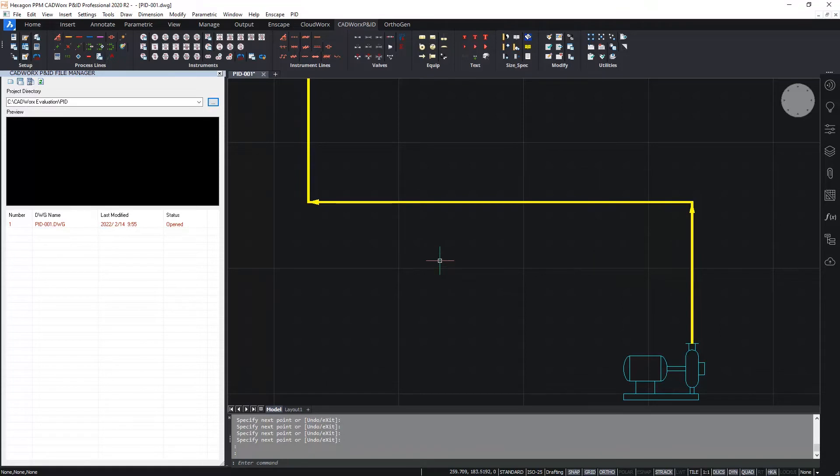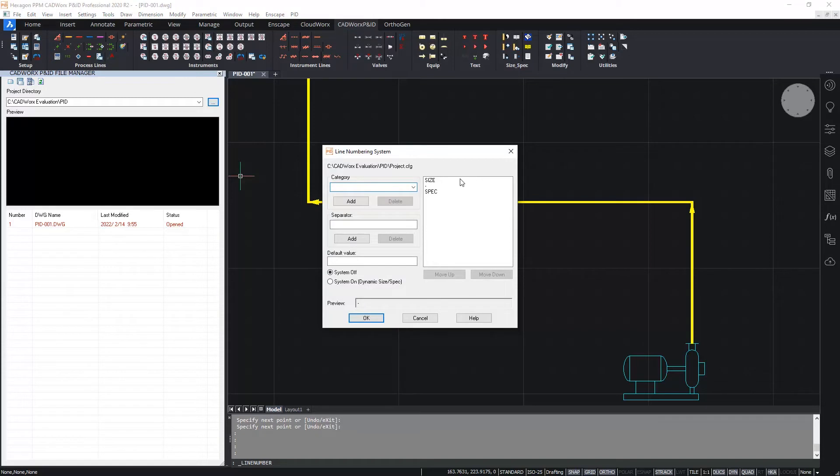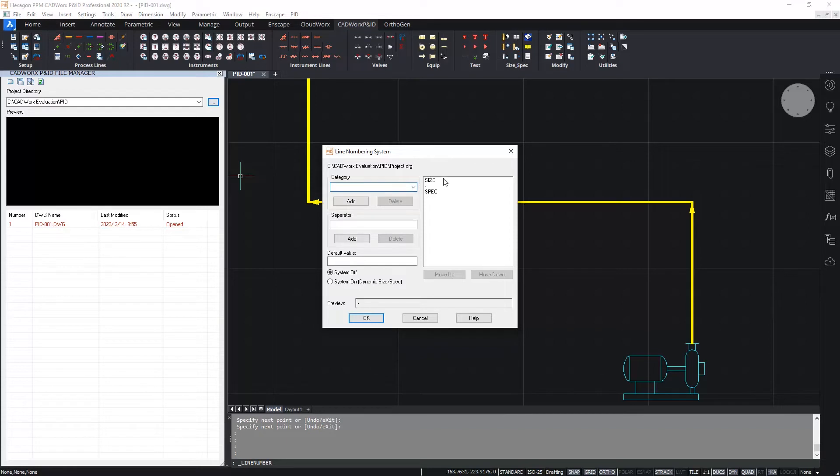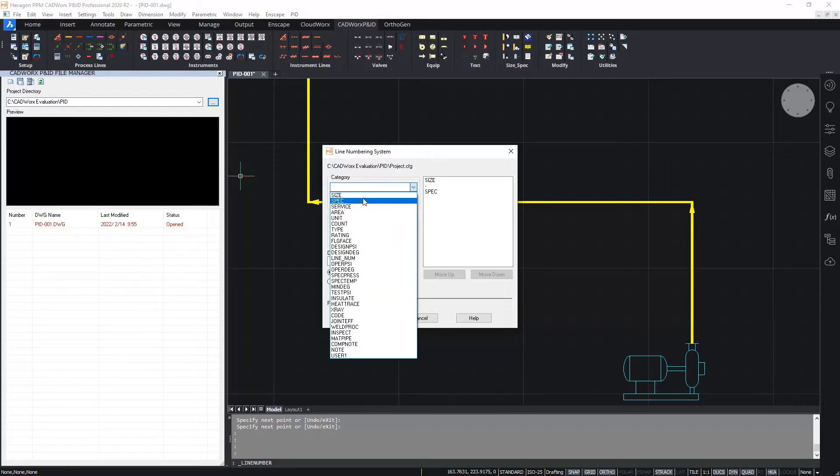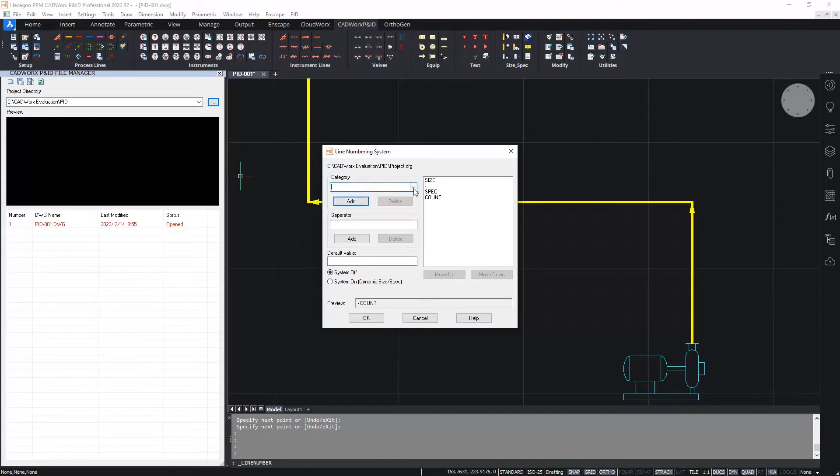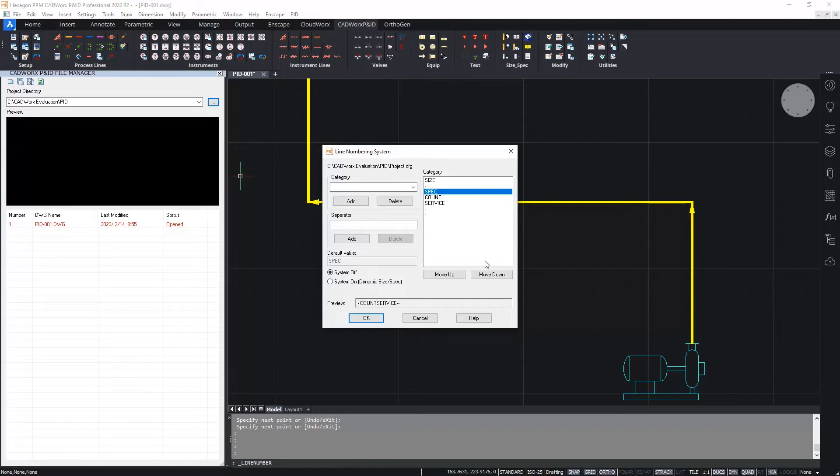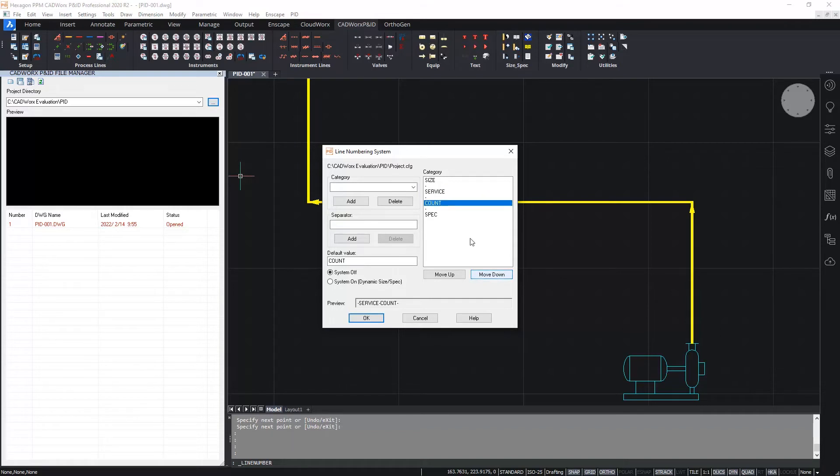However, for more consistent tagging, I'm going to configure a line numbering system. I'm going to select the line numbering system icon on the ribbon over here. And I will now set up my line numbering system. I can choose from any available category in the process lines table in the project database. I already have size and spec in there, so I'm going to add a couple more categories. Let's add count and let's add a service value as well. I'll add some separators to make the line number easier to read. And then I'll use the move up and move down buttons to adjust the order of those fields. So let's move spec right down to the bottom and then move count down below service. So I have size, service, count and spec.